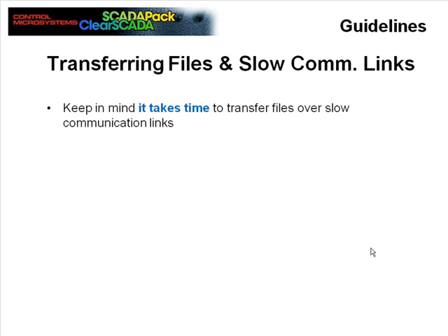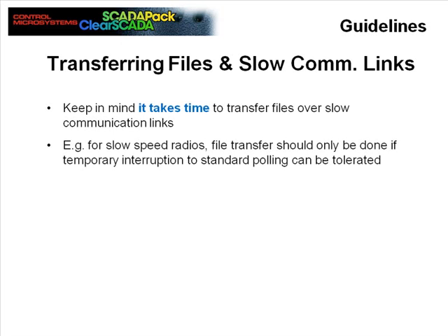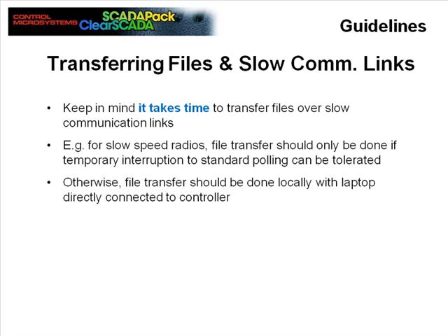Now when transferring files on slow communication links such as a serial radio link, keep in mind that it does take time to transfer files. The file transfer should only be done if temporary interruption to standard polling can be tolerated on these slow speed connections. Otherwise, file transfer should be done locally with the laptop directly connected to the controller.